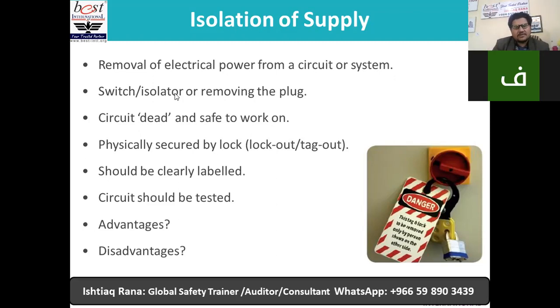Isolation basically is more effective in the sense that you remove the breaker, you remove wires, you remove the fuses, and that means you make sure there is no chance of anyone even starting up that breaker or something. But in lockout tagout, sometimes what happens is you just turn off the breaker and lock and put tag, but still there is a probability someone can open and turn on that breaker while you are working, God forbid, in that area.